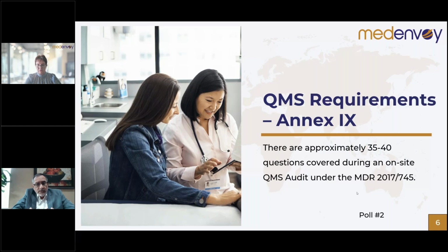During an on-site quality management system audit, notified bodies are covering approximately 35 to 40 questions, depending on the product type and classification. Audit duration can vary from a few days to a whole week, or 7-8 days, depending on the number of products and families and the classification. So we will go through the questions.